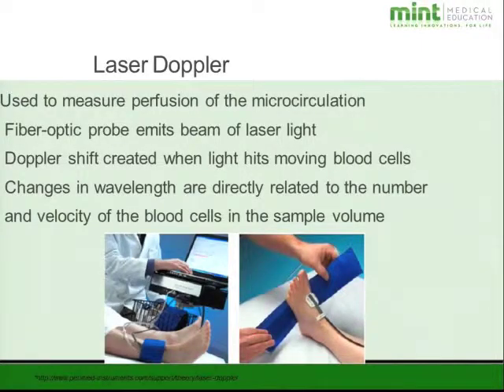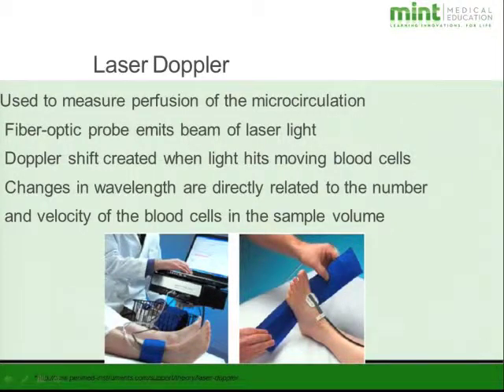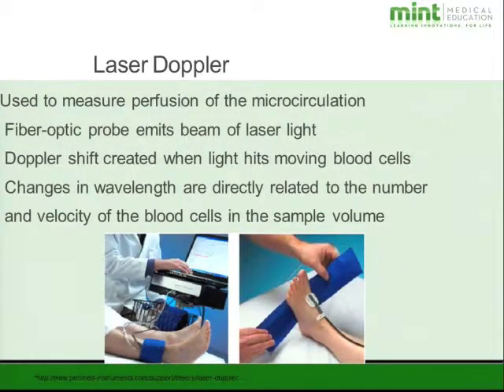Laser Doppler is another way to evaluate the microcirculation. A fiber optic probe is placed on the skin and held under a cuff. The Doppler shift is created when light hits moving blood cells, much like PPG waveforms. Changes in wavelength are directly related to the number and velocity of blood cells in that sample volume.